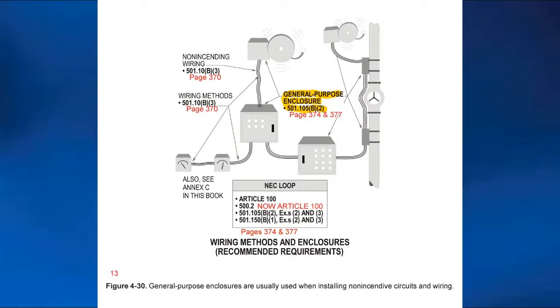And so it's a less hazardous location, so even if you create a spark, it's not going to ignite. That's how they can declassify it to a Class 1 Div 2, because more ventilation decreases the fuel that would cause an incident from a heat spark in that area.